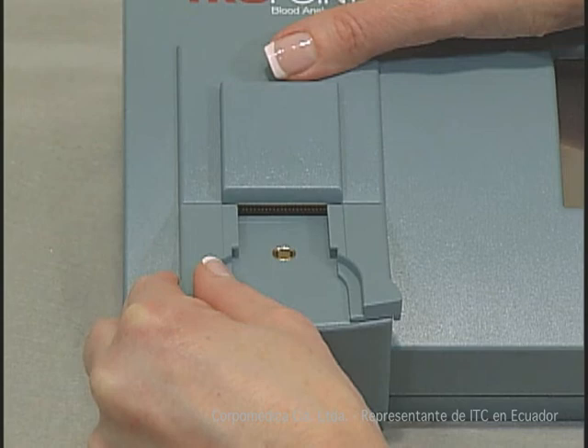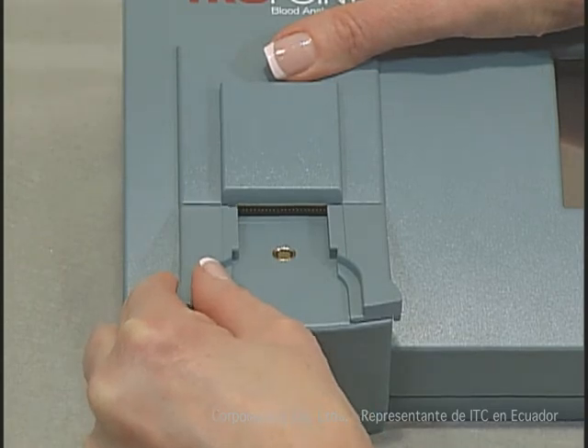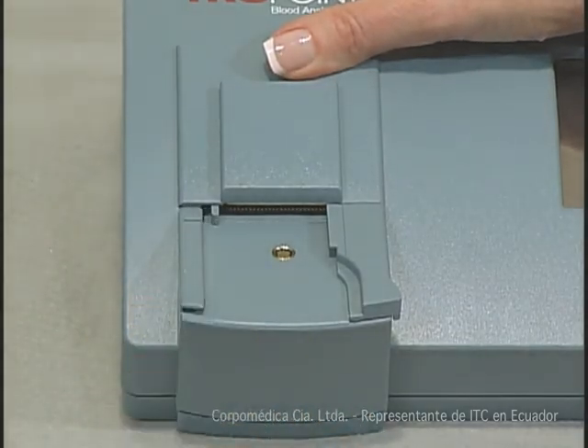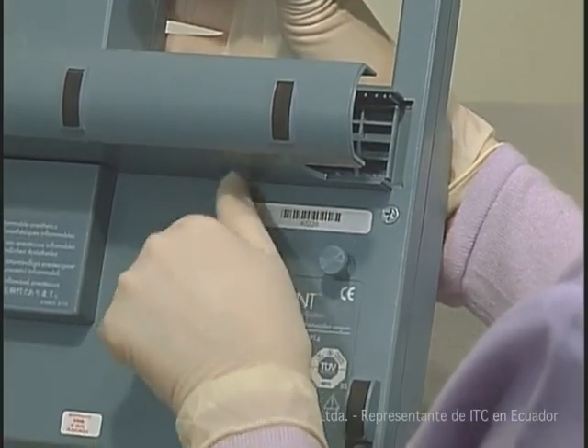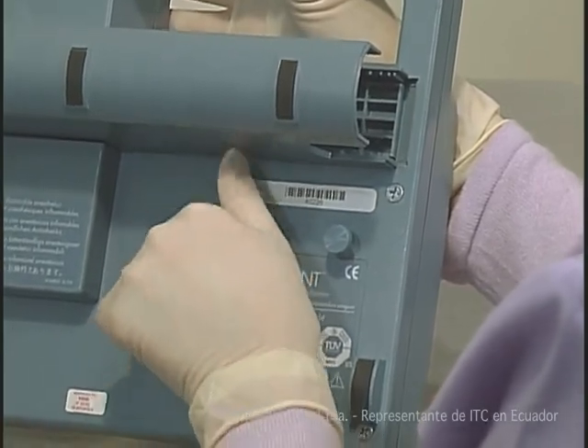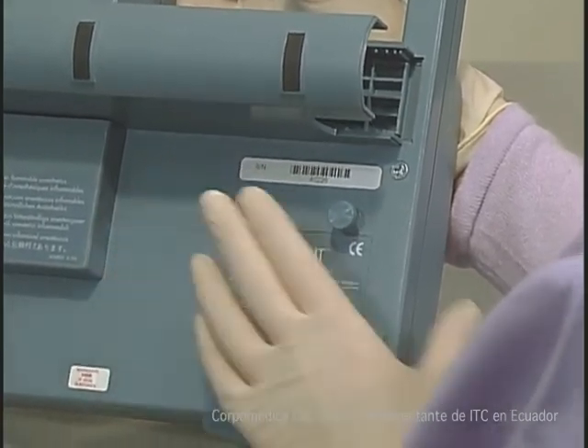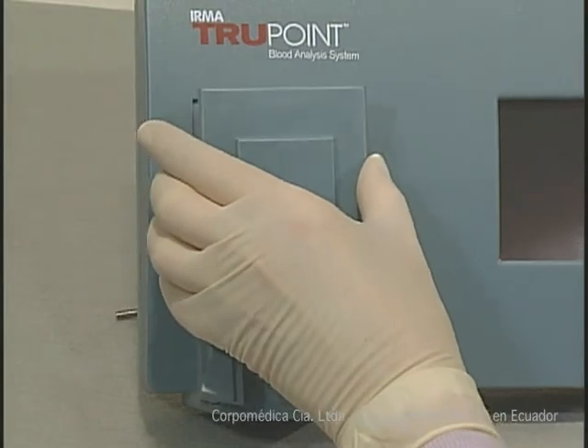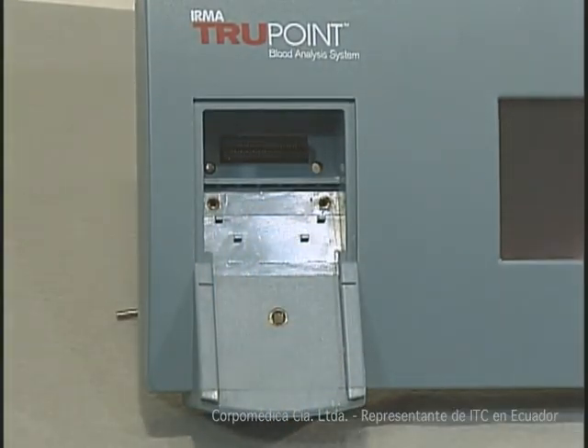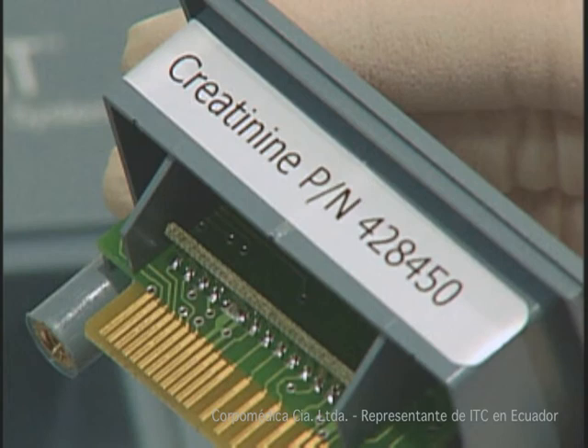If cleaning does not solve the problem, or if the edge connector has become contaminated, replace the edge connector. To replace the edge connector, remove the power source first, then remove the right and left cartridge guides. Loosen the two thumb screws on the underside of the analyzer and press against them to help loosen the edge connector assembly. Remove the edge connector assembly from the analyzer.